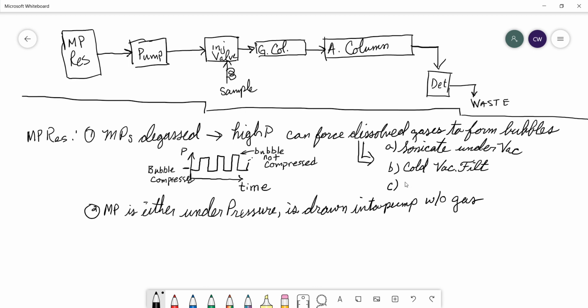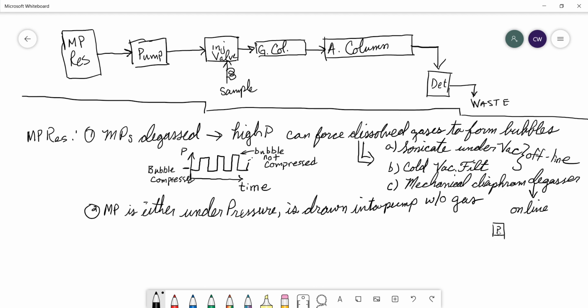Or we use a mechanical diaphragm degasser. Okay, these first two techniques are considered offline because we have to do them away from the instrument. The mechanical diaphragm or membrane degasser, though, that's an online technique. Okay, we put that between the reservoir and the pump. That way the reservoir mobile phase gets pushed into the degasser. The degasser removes any gases that are dissolved in it, and then we push it in.